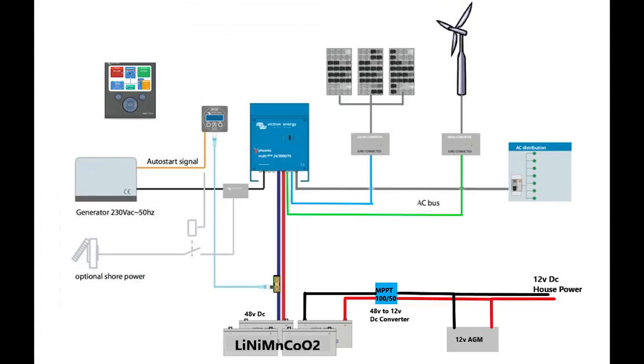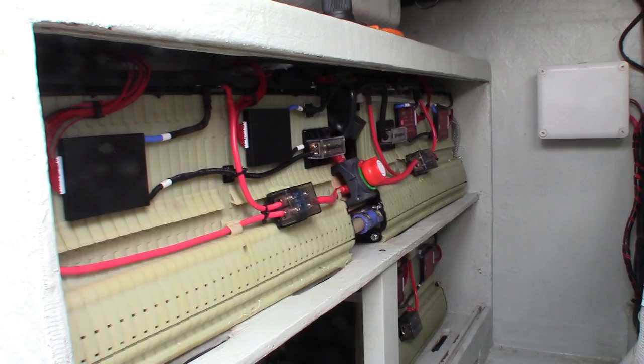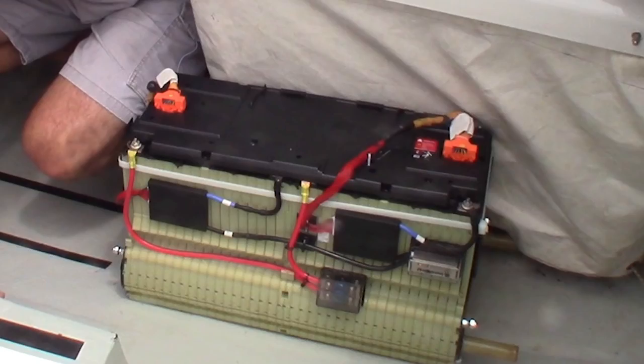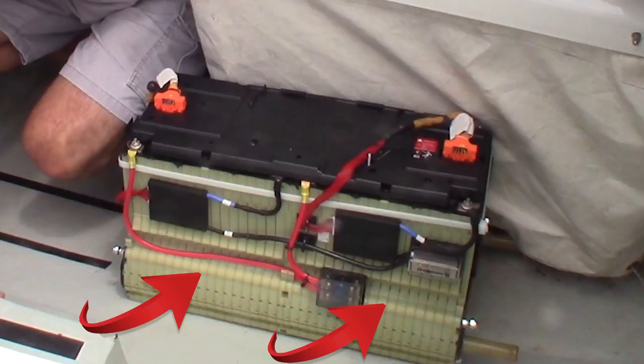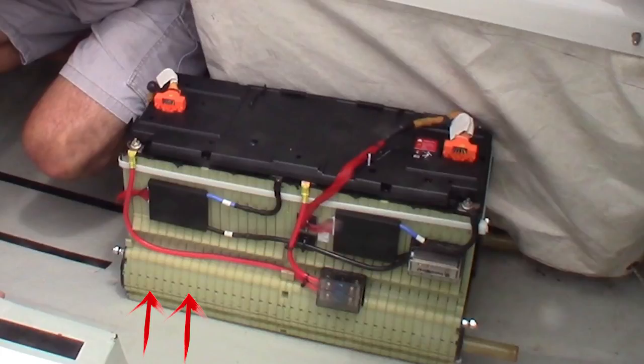So let's start off by talking about our storage system. This is where we put our power to store it. And in our case, we're using a lithium-ion battery bank. Let's talk about the components of our battery storage system. In our particular setup, we're using four modules. Each module consists of two batteries, which are just butted together. Each battery has 12 cells. Each cell is a nominal 3.4 volts per cell, which gives you 40 volts minimum, or 4.2 maximum for 50.4 volts maximum.